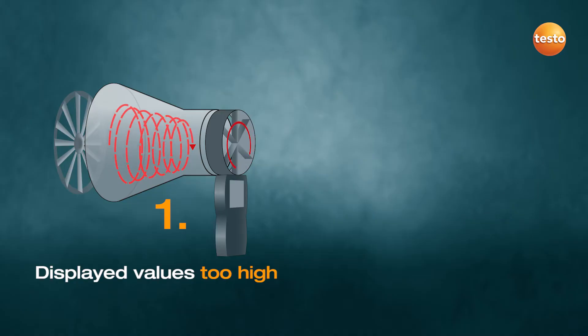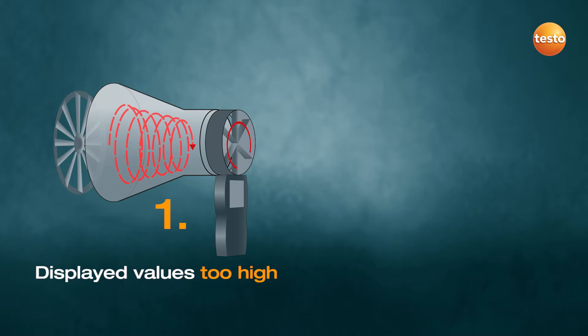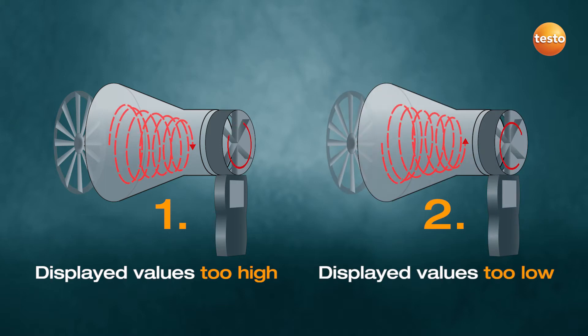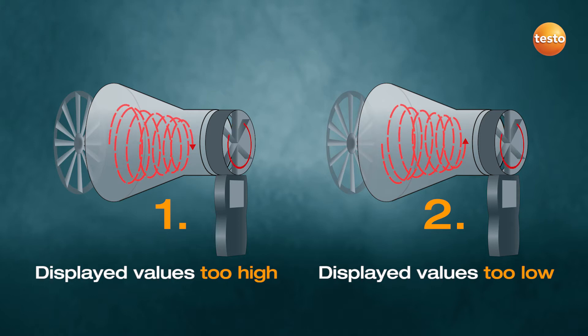Let's take a closer look at what happens. First: if the direction the swirl rotates is the same as that of the vane, the flow hits a larger cross-sectional area of the individual blades, making it accelerate too fast. Second: if the direction the swirl rotates is opposite to that of the vane, the flow passes between the individual blades and doesn't accelerate properly. The result is that an inadequate flow velocity is displayed.